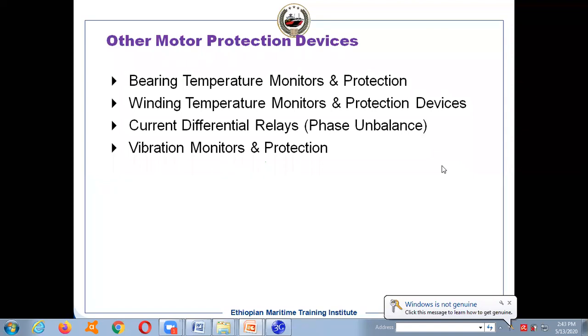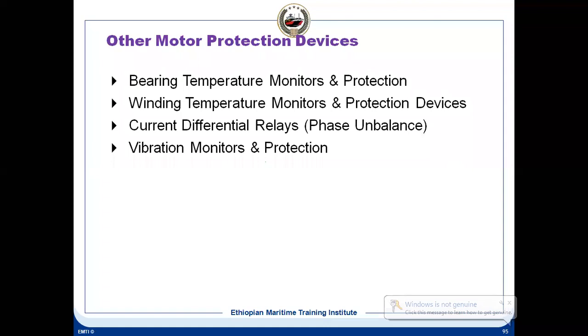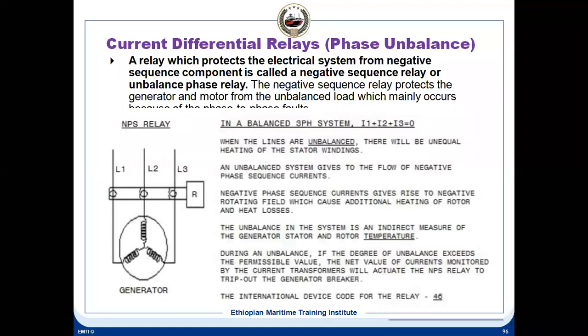So, bearing temperature, winding temperature, differential relays, phase balance, and vibration monitors. Let's see how they work, starting with vibration monitors and phase balance. A relay which protects the electrical system from a negative sequence component is called the negative sequence relay or unbalanced phase relay. The negative sequence relay protects the generator and motor from unbalanced load.